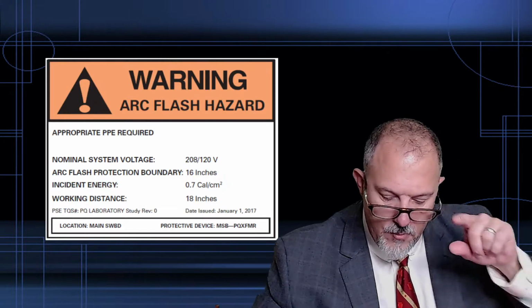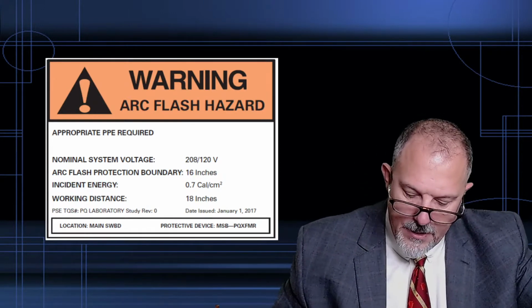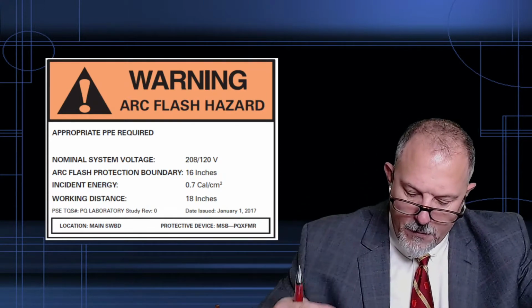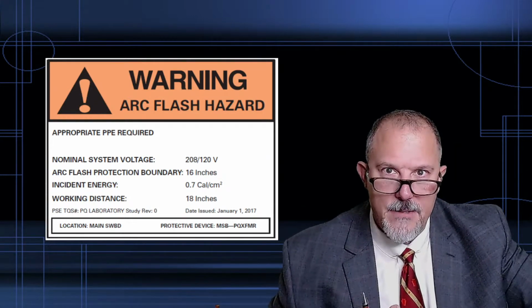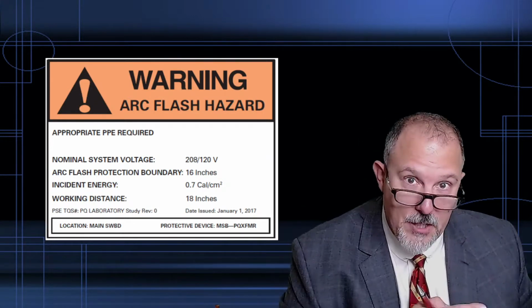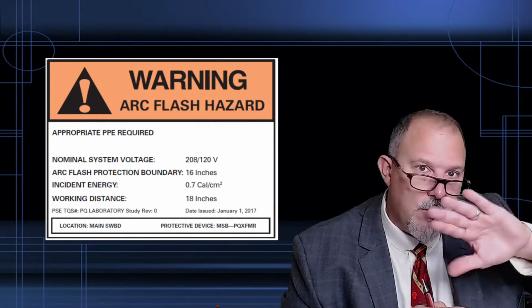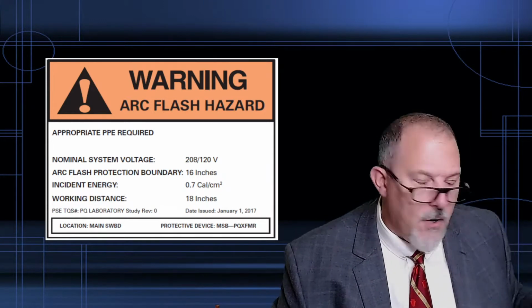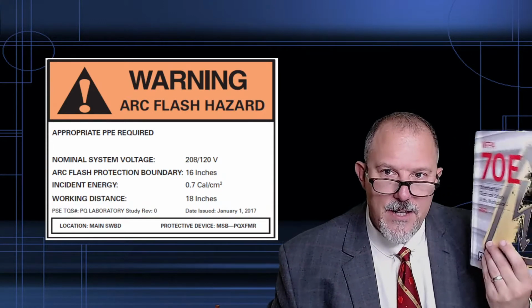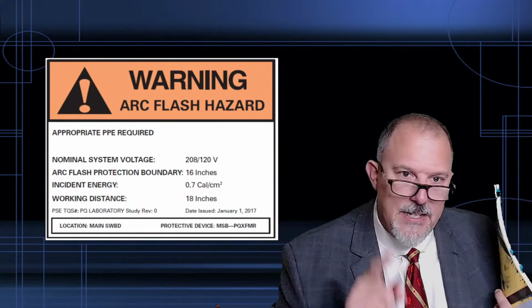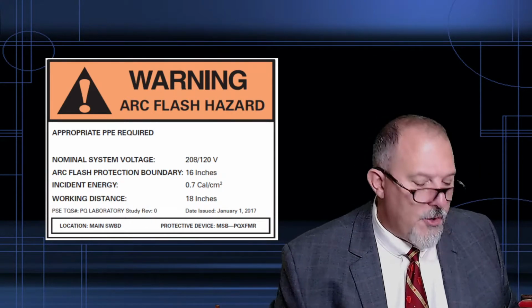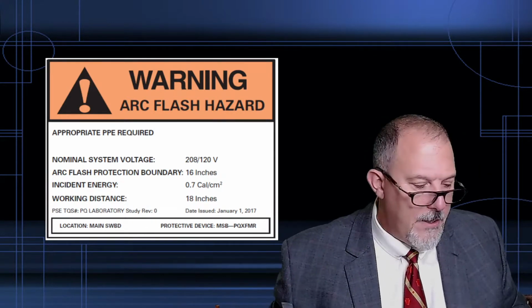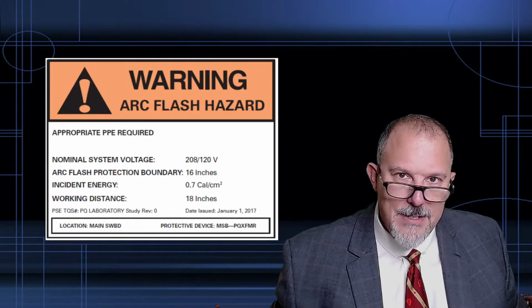The Electrical Code says in B that you have to have the voltage, the available fault current, the clearing time, and the date. But the exception says I don't have to do that if I follow an industry recognized practice, which is 70E, and 70E does not require the date, although many of us put the date on. Why would you not put the date?